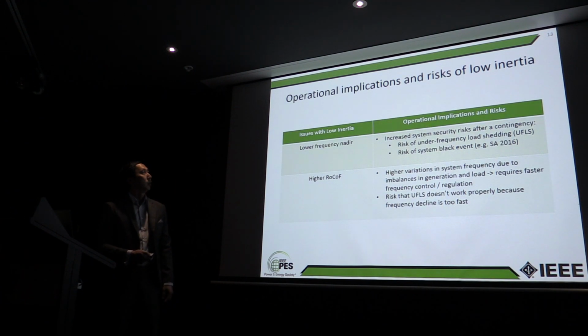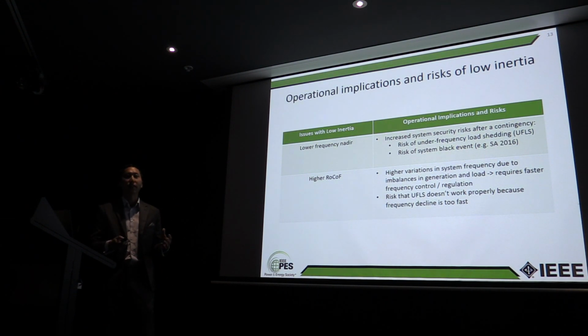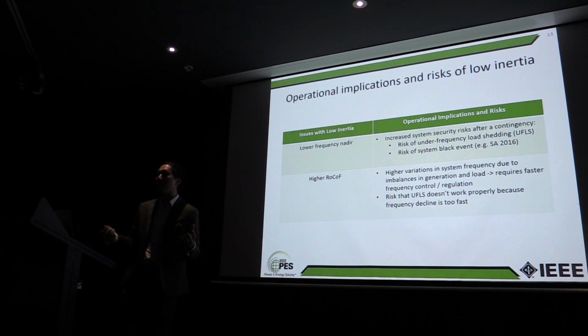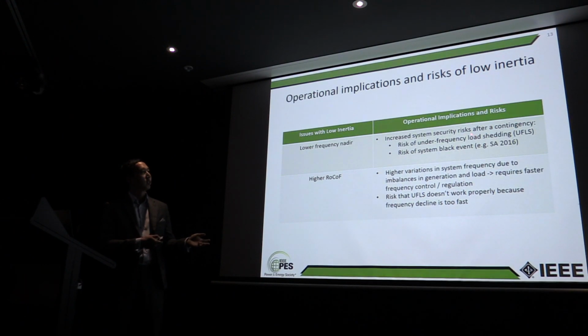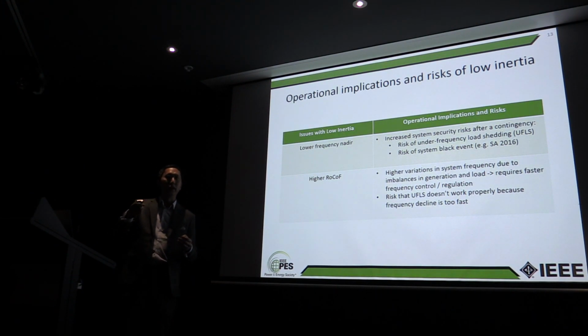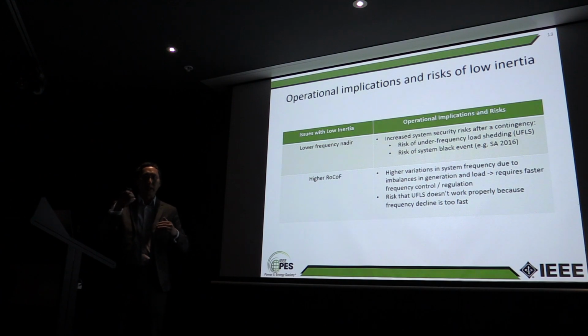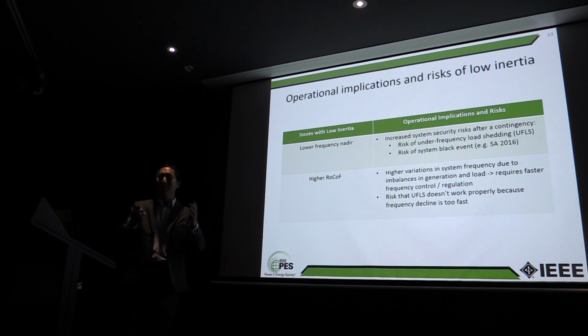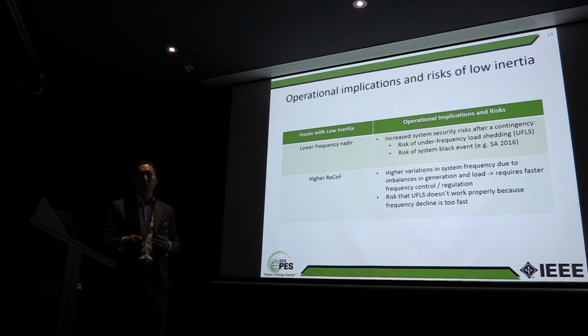And that's an important point. So here's just a summary of the operational implications and the risks that are associated with having low inertia. The risk of having a low frequency nadir is that we have increased system security risks after a generator drops off the system. What that means is we can risk under frequency load shedding. That's basically a protection system that if the frequency goes down too far, it will drop off load in the system. So we would knock off a few loads in a couple of suburbs or whatever, and that's supposed to get the power back to balance. Because we've lost 300 megawatts, we need to gain that 300 megawatts back somehow. And if the frequency falls too far, you can try to get power balance by knocking out the loads.